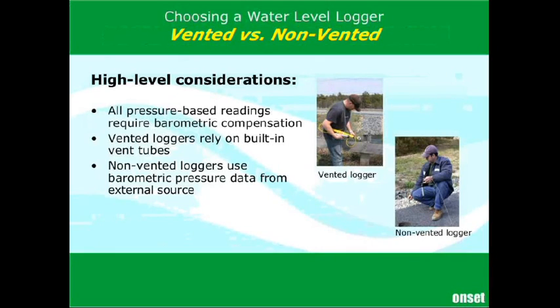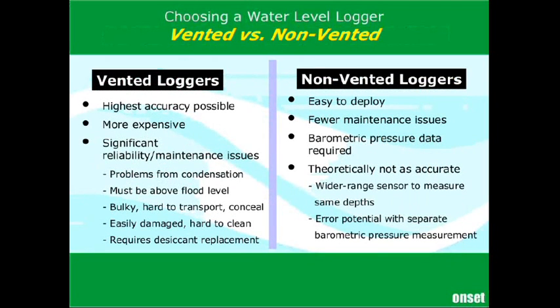In the non-vented logger, the back side of the diaphragm sees a vacuum, and the front side sees the sum of barometric pressure plus the water pressure. To accurately measure water level, barometric pressure must be logged and subtracted from the non-vented logger pressure data. There are pros and cons for each approach. The vented logger has the highest accuracy. It requires the smallest range transducer. If you're in 5 psi of water depth, you simply need a 5 psi sensor.